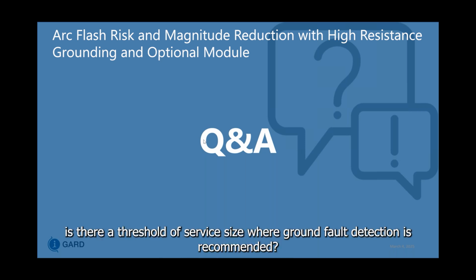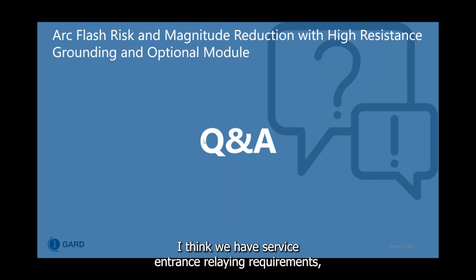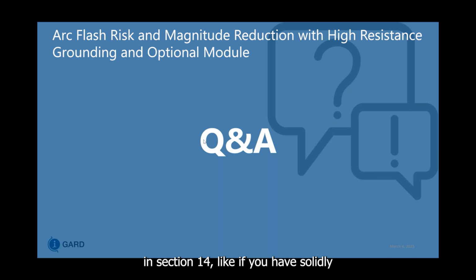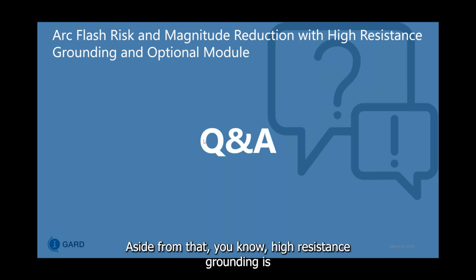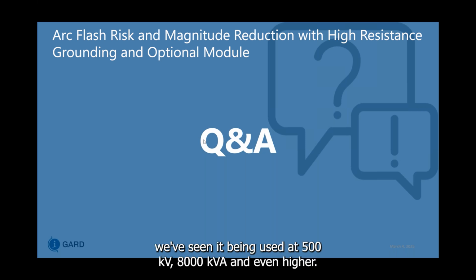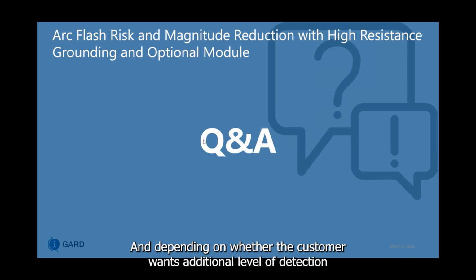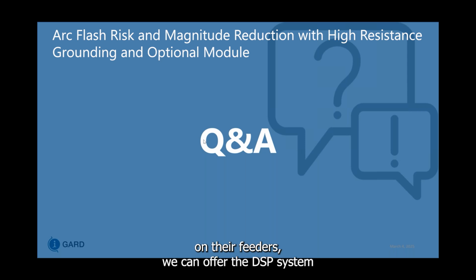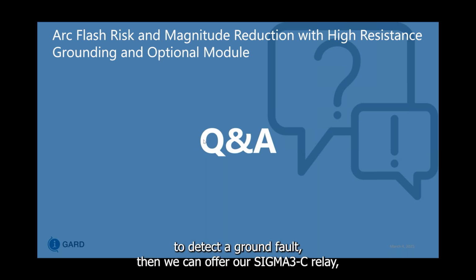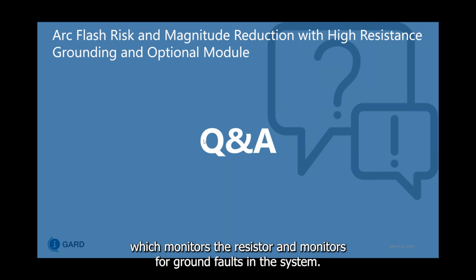Is there a threshold of service size where ground fault detection is recommended? I think we have service entrance relaying requirements in section 14, like if you have solidly grounded systems. Aside from that, high resistance grounding we've seen it being used at 500 kVA, 1000 kVA, and even higher. And depending on whether the customer wants additional level of detection on the feeders, we can offer the DSP system. If they just want to be able to detect a ground fault, then we can offer our Sigma 3C relay, which monitors the resistor and monitors for ground faults in the system.